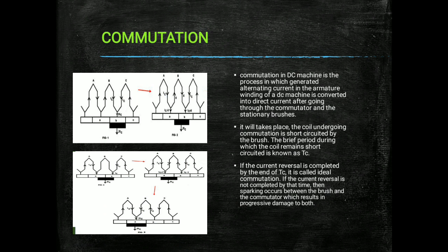If the current reversal is completed by the end of tc, it is called ideal commutation. If the current reversal is not completed by that time, arcing or sparking occurs between the brushes and the commutator, resulting in damage to the commutator and the brushes. Here we can see five images of the commutation process.